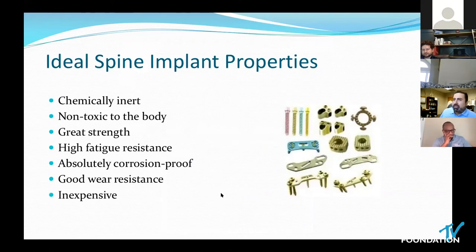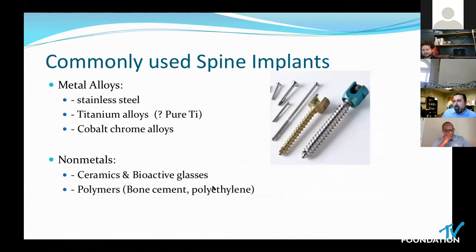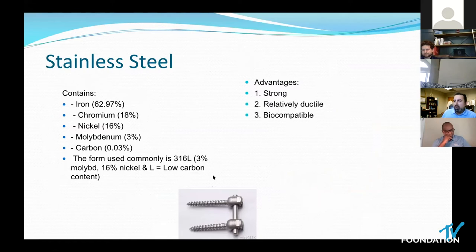What are the implants we put in? Relatively straightforward concepts: it has to be non-toxic, strong, wear-resistant, and inexpensive. Among the ones we use: stainless steel, titanium — often the most common — and cobalt chrome. When it comes to other implants, we have polymers and ceramics. Steel was the original instrumentation construct. It had the advantage of being very strong and ductile — able to resist deformation to a large amount before it failed.